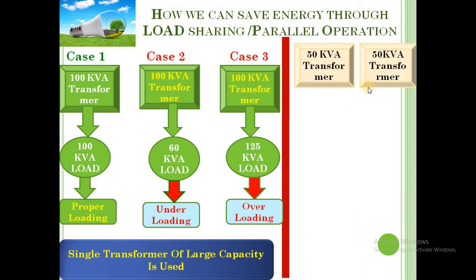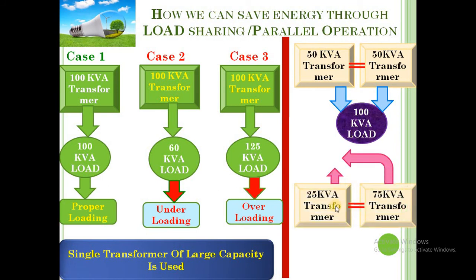So this is what happens if we use a single transformer of large capacity or lower capacity for supplying a varying load. Now next, if we do parallel operation of transformers, here two transformers are connected in parallel. So a 50 kVA transformer is there, again a 50 kVA transformer is there. They are connected electrically to supply the 100 kVA common load. So 100 kVA common load आहे की जो सप्लाय केला जातो 50 kVA ट्रान्सफॉर्मर आणि दुसरा ट्रान्सफॉर्मर 50 kVA चा. So these two transformers share the load of 100 kVA. Now second case, a 25 kVA transformer is there, a 75 kVA transformer is there. So together they can share the 100 kVA load. So this is a parallel operation we can do.